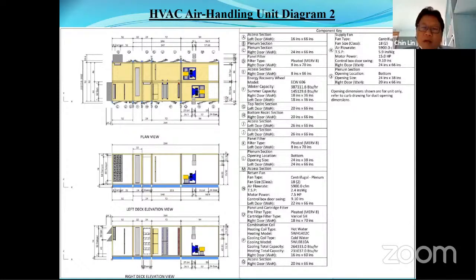I just want to put it in a very simple way to think about: the basis of design where we start is a MERV 14 standard unit, pretty much something they've been doing for a number of years. If we go to MERV 16, the unit would have to have larger motors in order to push the air through the filter, because it's a much finer filter.